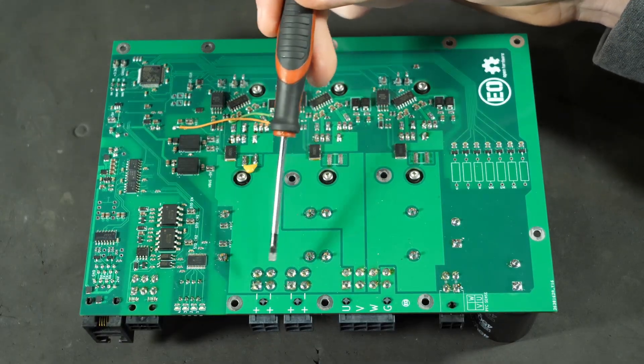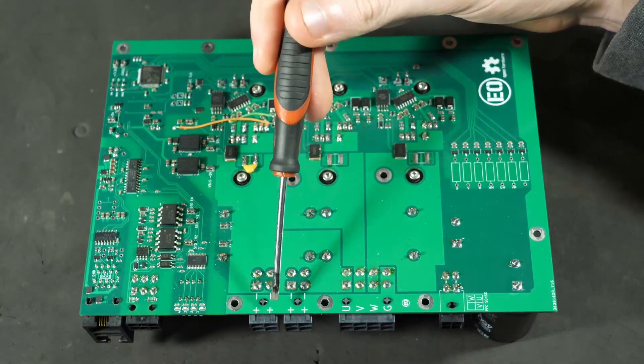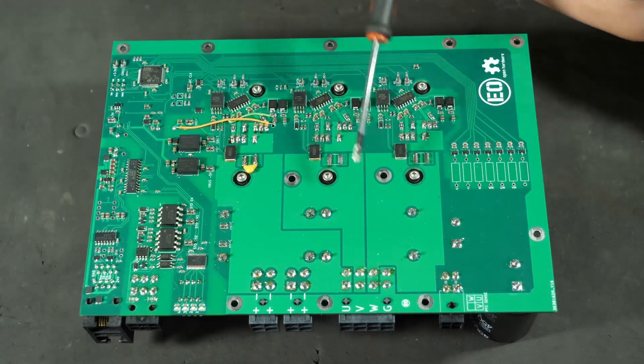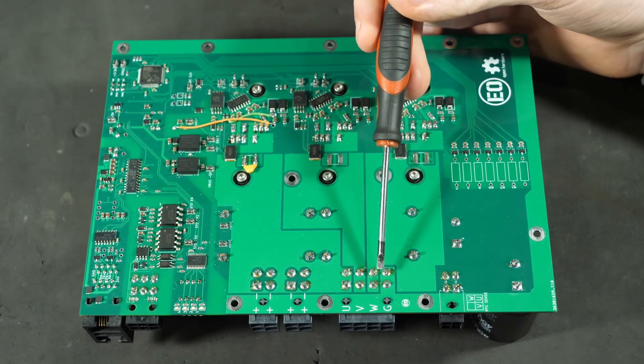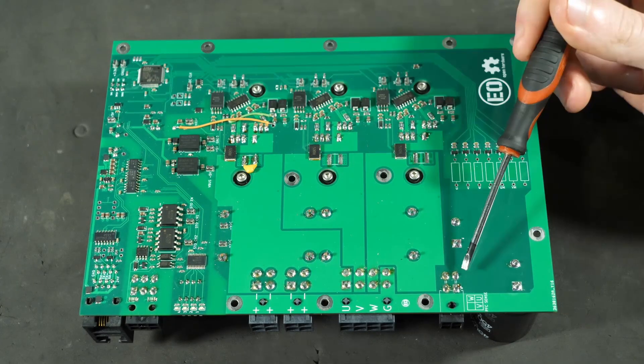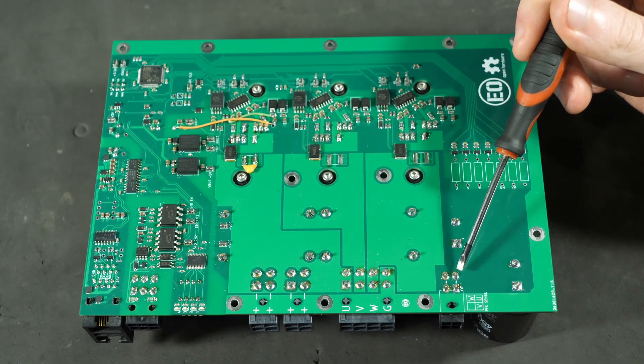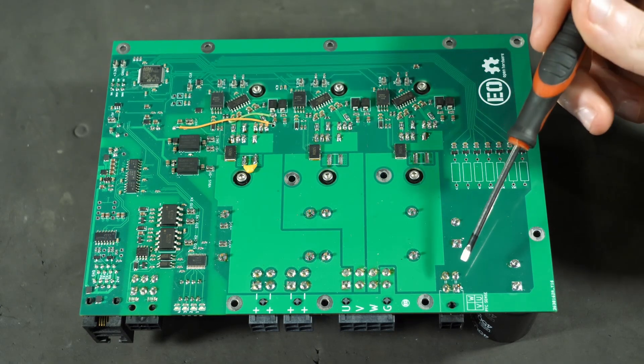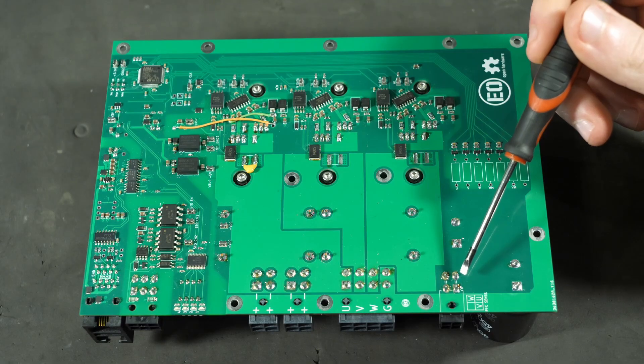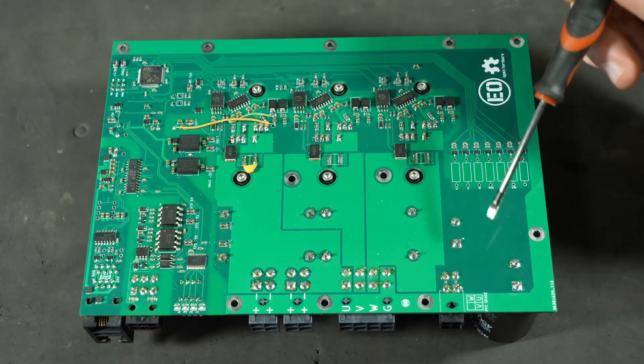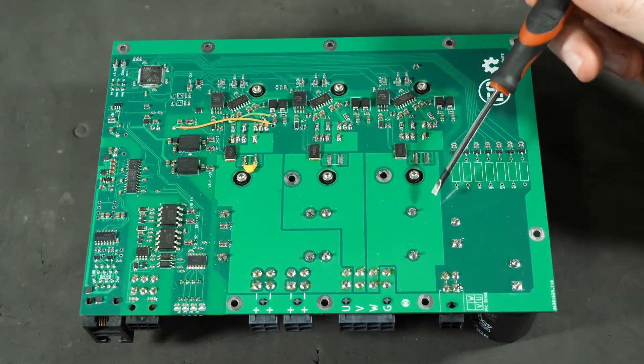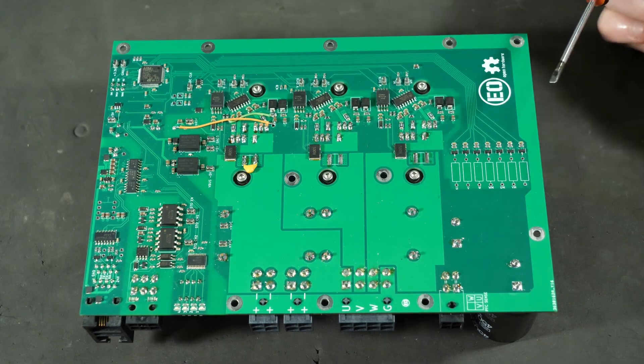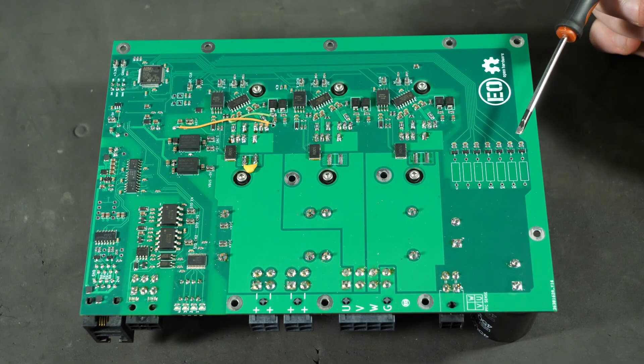These two large connectors are for connecting to the DC bus where these drives get their main power, and this large connector is for outputting to the motor phases. This last connector is for voltage sensing before a line reactor, so these drives can also rectify power from a wall to supply the DC bus. This is a super cool function that I don't think I've seen anywhere before, which is a bit concerning since that usually means there's a reason not to do it, but we'll see eventually.